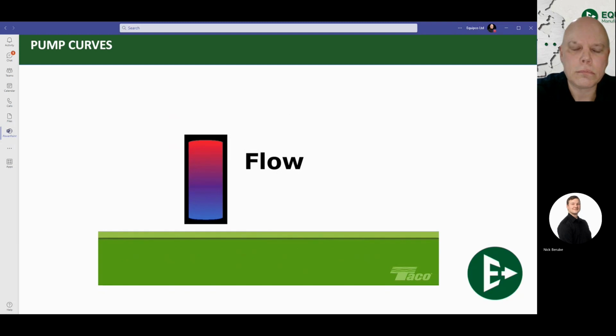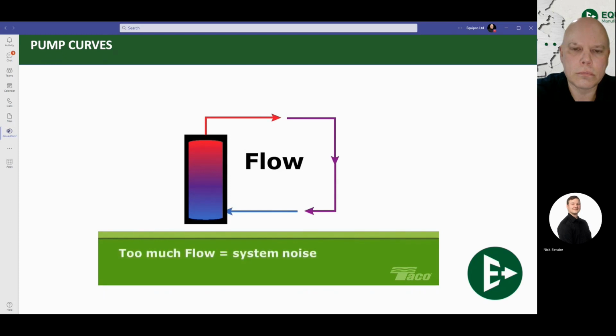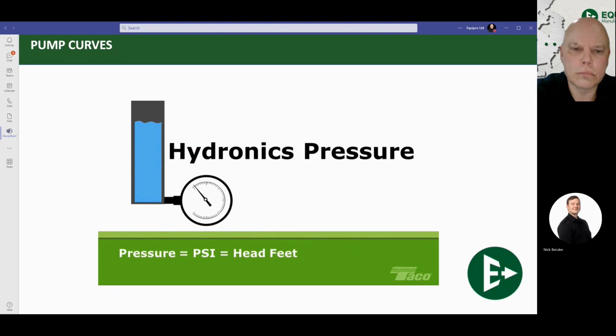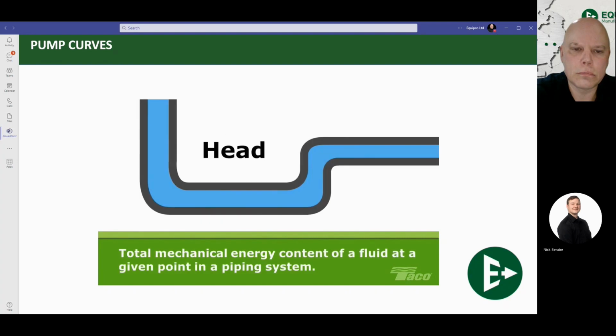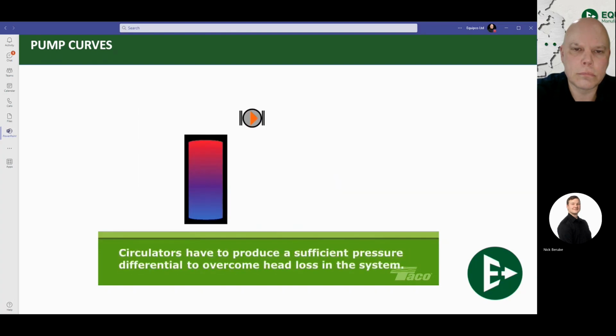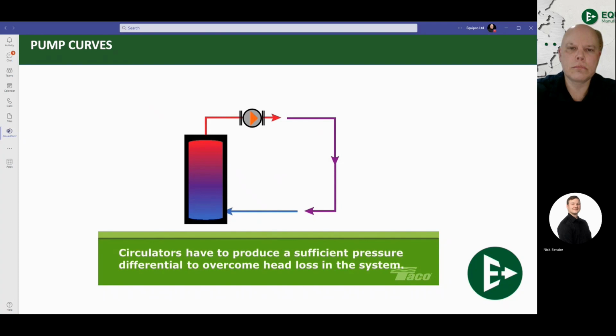Flow, measured in gallons per minute, is the rate at which water must be moved to carry heat throughout a hydronic system. Too much flow results in system noise. Too little flow means insufficient heat will reach at least some areas of the building. Pressure is usually measured in PSI, pounds per square inch. But in hydronics, we calculate pressure in terms of head pressure or head loss as measured in head feet. Technically, head is the total mechanical energy content of a fluid at a given point in a piping system. A circulator has to produce a sufficient pressure differential to overcome the pressure or head loss created in the piping by friction and by the various valves and fittings in the system.